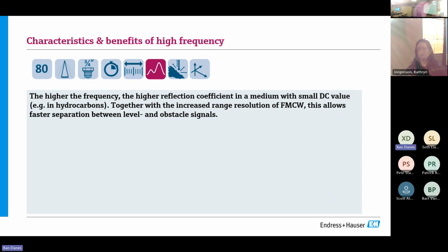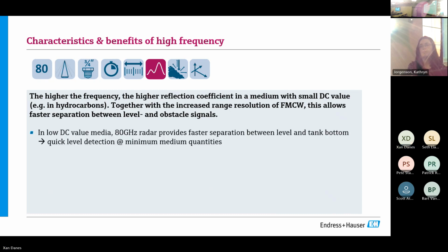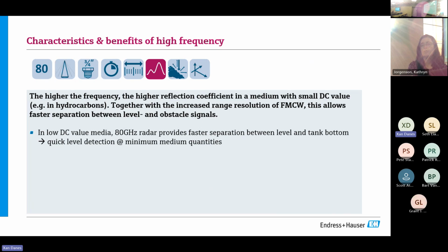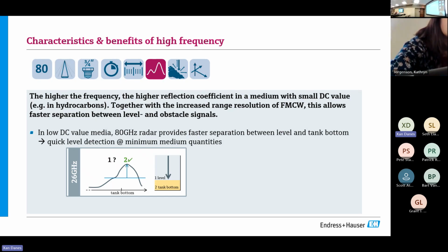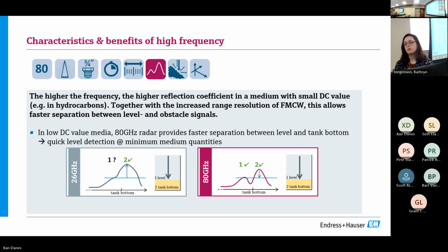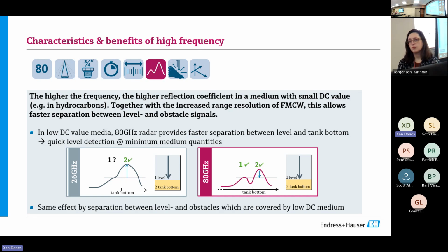This is a nice segue with the LPG question and less reflective media. At higher frequency, we get a higher reflection coefficient, especially in mediums, both solid and liquid, with small dielectric constants. So we get faster separation, a faster measurement when we go from, say, an empty tank bottom to a thin layer of these low dielectric products on top of it. We get quick level detection at minimum quantities, because we're getting much more reflection off the low dielectric and much less that gets permeated or transmitted through it. So we're able to measure lower dielectric products quicker.